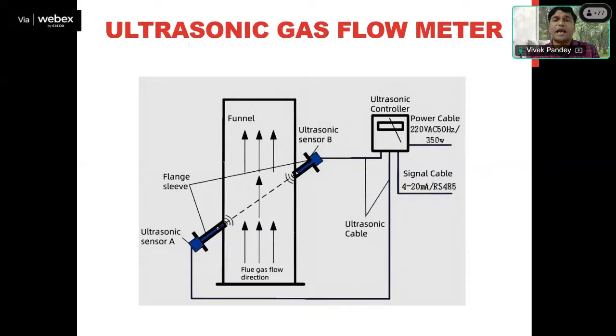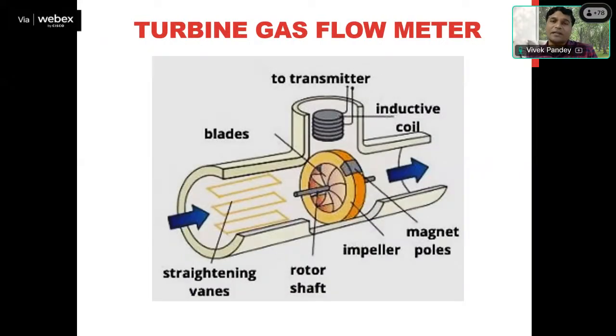And this is basically calibrated, or you can say calculated in terms of quantity of gas. So this is the basic operation. I'm not discussing the operation in detail, but this is the basic operation of these ultrasonic gas flow sensors, gas flow meters. Now, another technology which is very commonly used is the turbine gas flow meter.